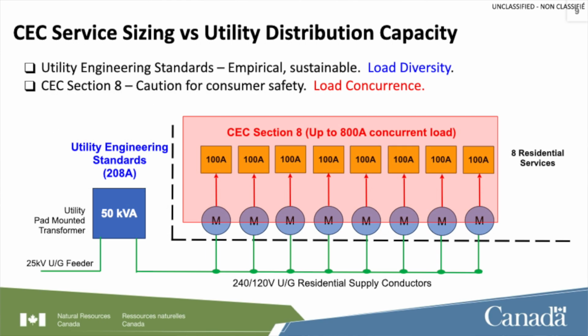So this is really a tale of two cities if we get into it, because we have the Canadian Electrical Code that says everything's always operating all at once, our worst case scenario. The utility engineering standards say differently. It's like, oh no, there's no way that everything's always operating at once. They're far more pragmatic. So that can also be a problem when we're going towards electrification.